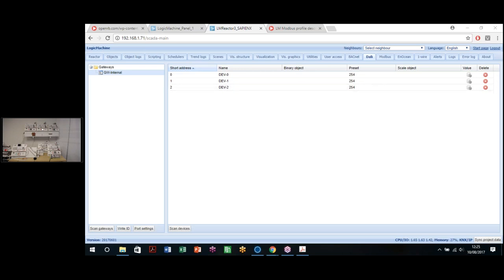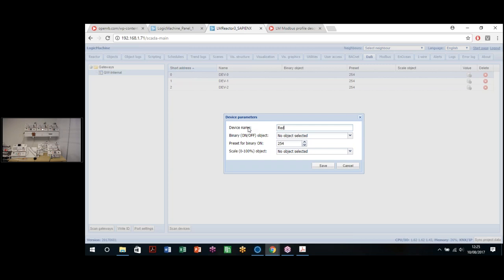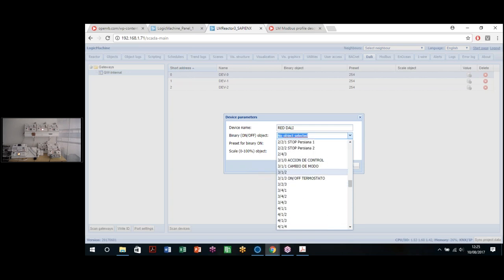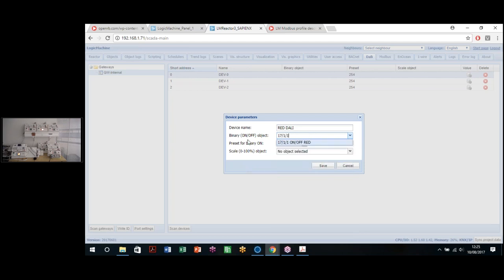Here we go. Here we have the three different ballasts, if we might. To configure this ballast and to begin the control of this installation, we're going to click on every ballast and change the name. In this case, let's put it to Red DALI. Let's turn off the light a bit so we can see it better. We change the address to 17.1.1 because it's the on-off object, and we have the scale object 17.3.1. Red value, and we save.